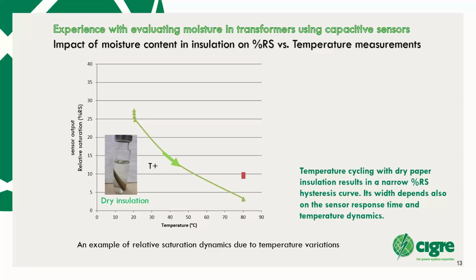Very, very important when we talk about the importance and the influence of moisture is to know how the hysteresis curves of moisture cooling down and moisture going back into the solid insulation are represented. Capacitive sensors which are online in a transformer do not only measure moisture in oil, they measure moisture in the solid system, in the system of both. Here we can see, for example, a dry insulation in insulating oil. And the hysteresis curve is very, very narrow because there is nearly no moisture which can go out and then go back. The situation will be quite different if we have wet insulation.